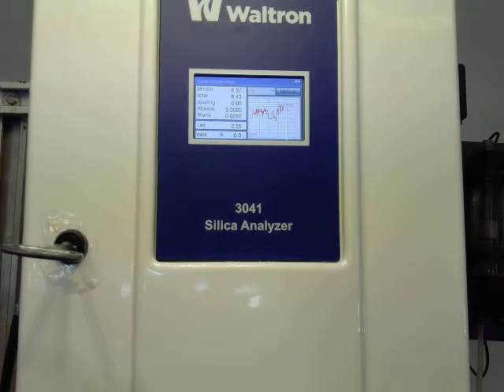And then the main thing that we're going to be looking for on this screen is once we add our third reagent, our color reagent, we should see a big drop in the sensor value. We should see a nice drop on the graph, basically indicating that, hey, there's silica present in the sample, it's forming color, and again, that's what we're trying to measure.